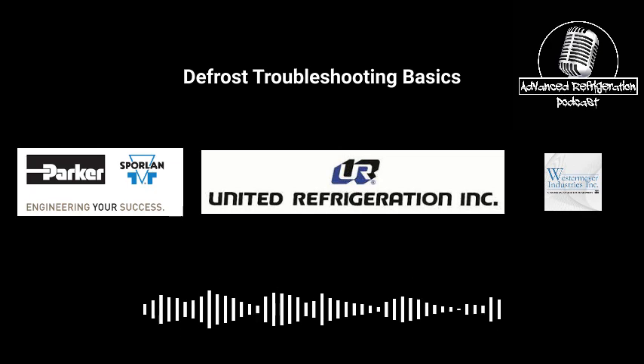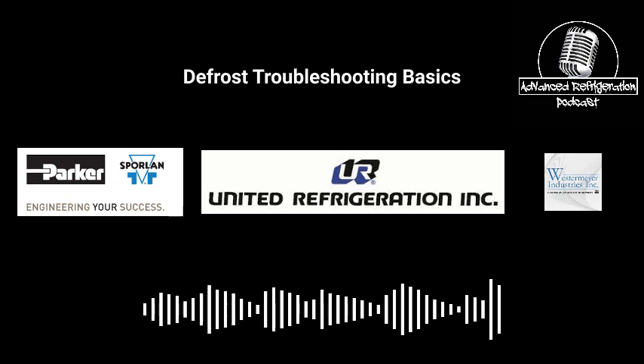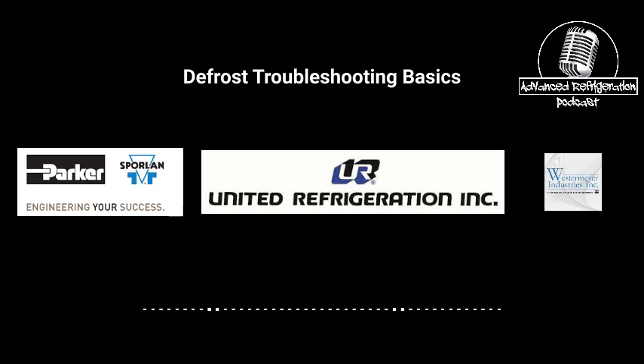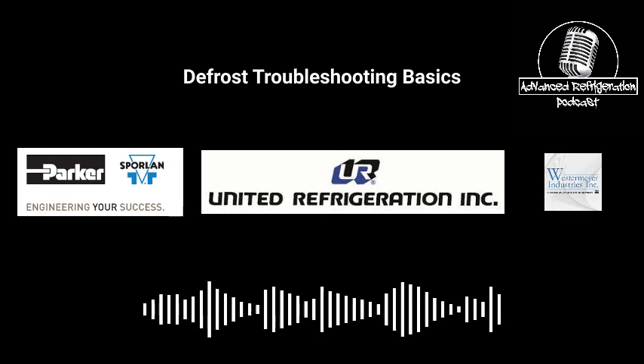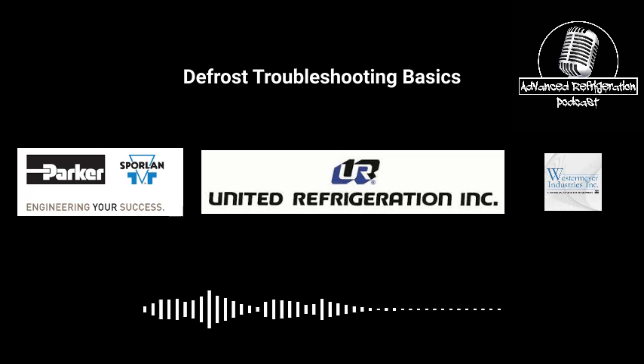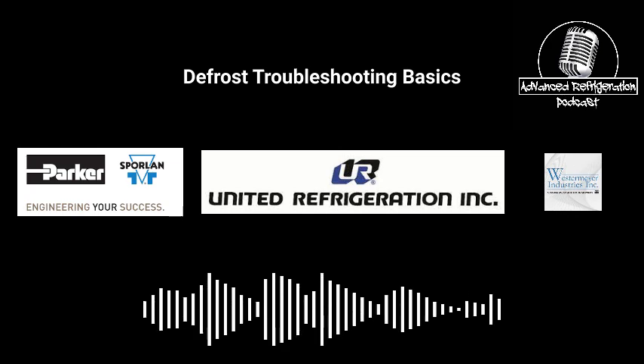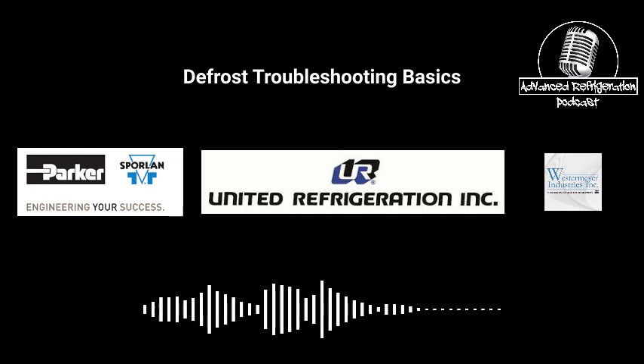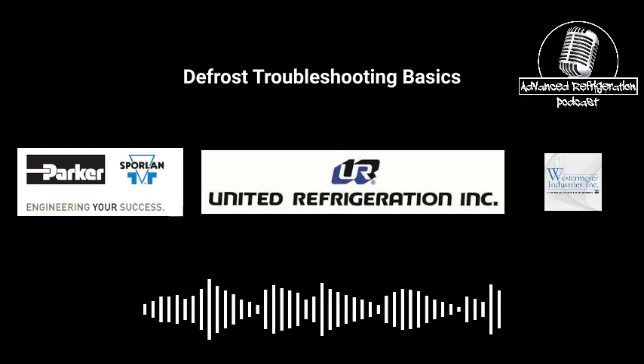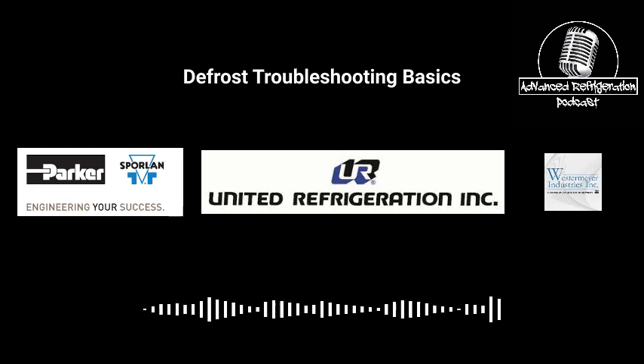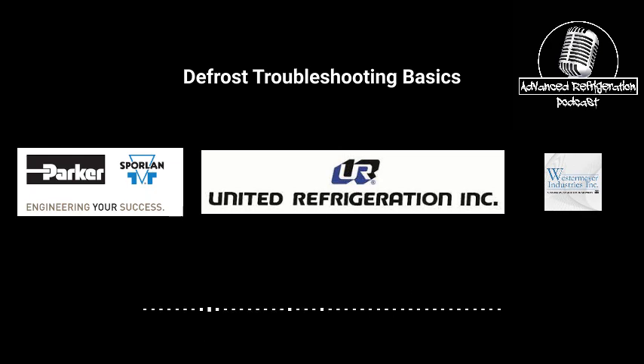And then when it turns back on, all of a sudden, oh, I don't know, every day at 12 o'clock, I end up having a ton of flood back, which ends up taking out my compressors. And like I said, you might not notice it at first, no erratic liquid level, because that'll happen too. Typically, if you have your liquid line solenoid feeding, not only is your liquid level going to change in your receiver, because you're basically filling up that whole line set and the whole coil with straight up liquid, but on top of it, you have the suction that ends up dropping like a rock, because you just have so much liquid that then needs to get back to the rack, and the only way it's getting back is through the suction, and there's no controlling factor.